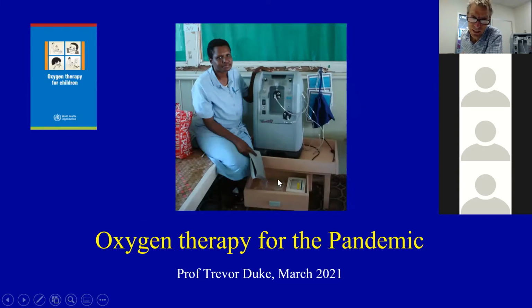He made these stands. It's got a drawer in the front that you can put your oxygen equipment, the tubings and everything in. And this was very important because that means that the concentrator is up off the floor. So it's not getting dirty and dusty like the floor. And you can clean around it very easily. And I would encourage hospitals to make such stands. They have to be strong because the concentrator itself weighs 25 kilos. So it needs to be a fairly strong stand.